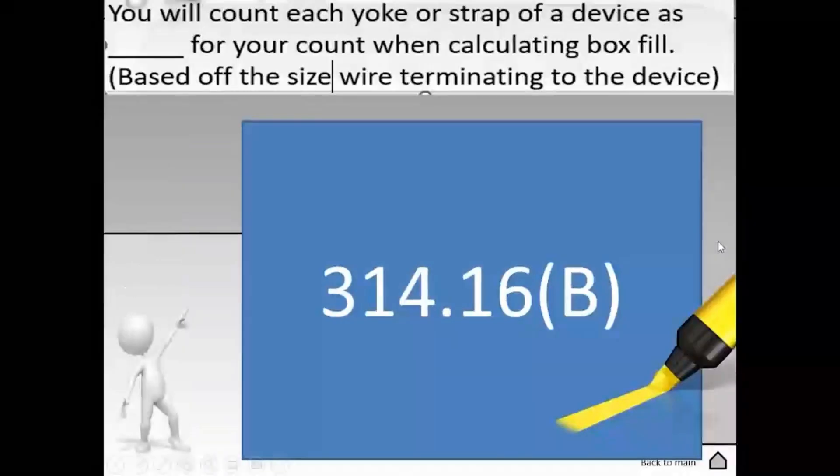And to find this one, we're going to head to 314.16b. And I want us to do some strategic highlighting here if you are allowed to highlight in your codebook. So when we get there, we get to 314.16b4 specifically.